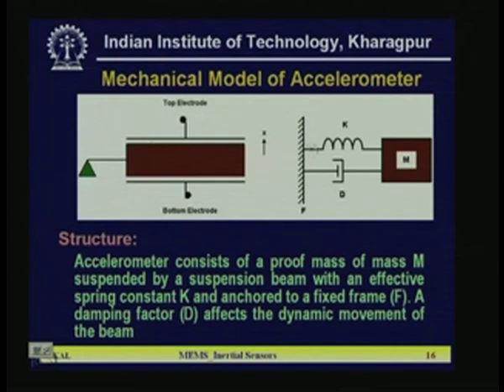On the left side you can see that two diagrams are shown here. The left one, the big filled thing, is basically the proof mass. The proof mass is held on a pivot with a flexure, and at the bottom and top there are two electrodes, a top electrode and a bottom electrode. Now, if this structure moves, then obviously because of the spring action of this flexure, the pivot will also move. So, accordingly the capacitance of the top and bottom electrodes will change. On the right side is a mechanical model of the accelerometer. Here is the proof mass M, which is fixed with a spring constant K.